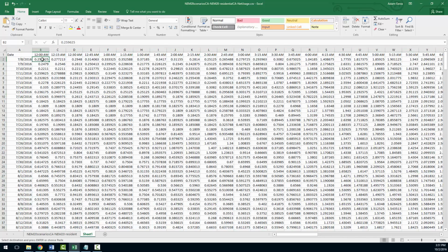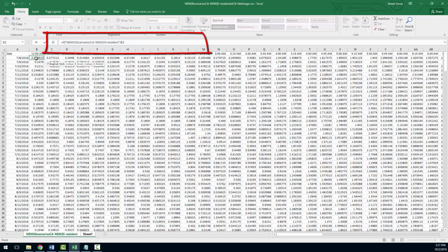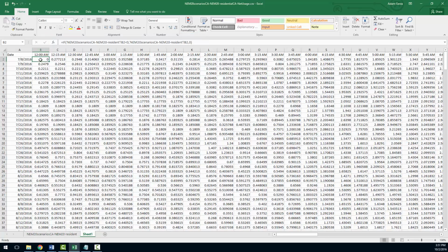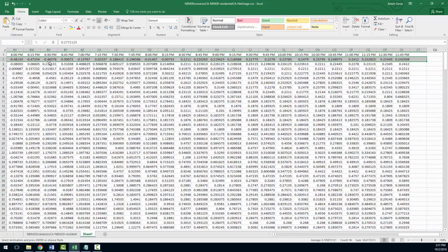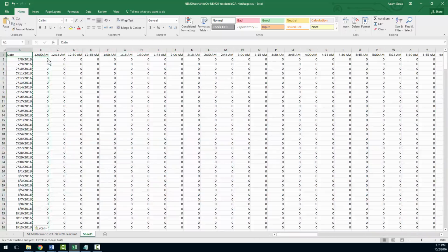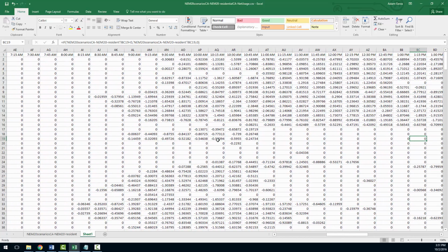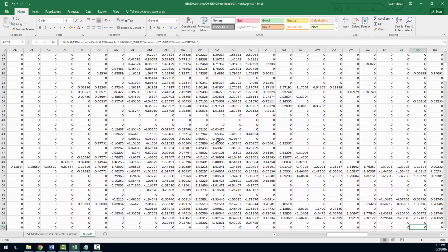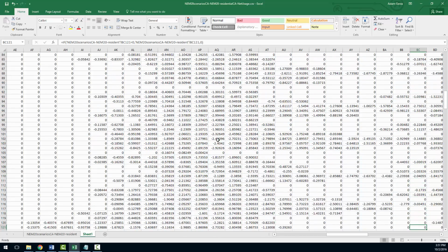And now I'm going to write a formula that says if, referencing back to the original tab, this value is less than 0, then give me that value. And if it's not, give me 0. So if I wrote that correctly, basically it's going to only show the negatives. So I'm going to copy that all the way down. I'm going to snap this across to the entire data file. And now as we scroll over through this data set, we should see some negatives. There they are, which basically represents all of the exported energy, or intervals where more energy is being produced and backfed to the grid than it is being consumed.